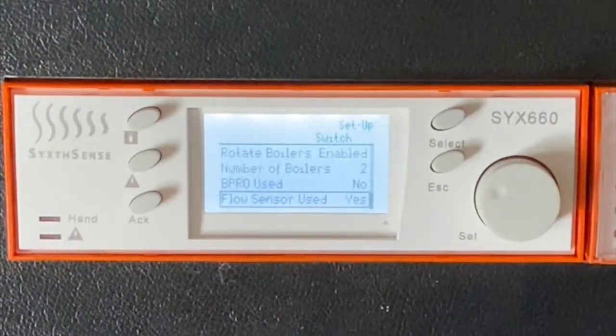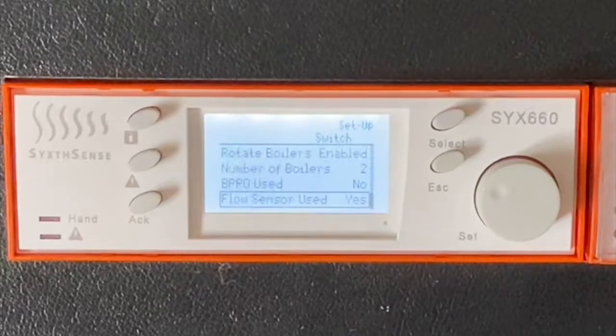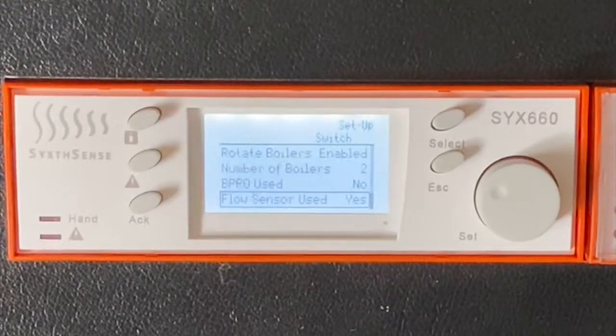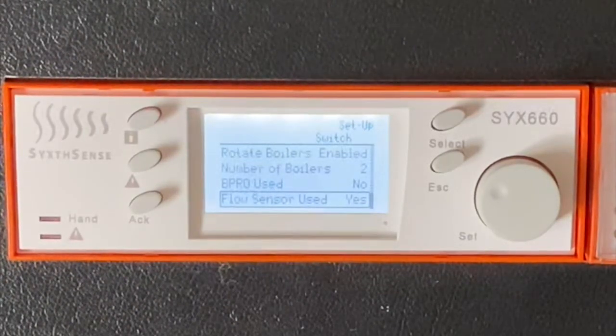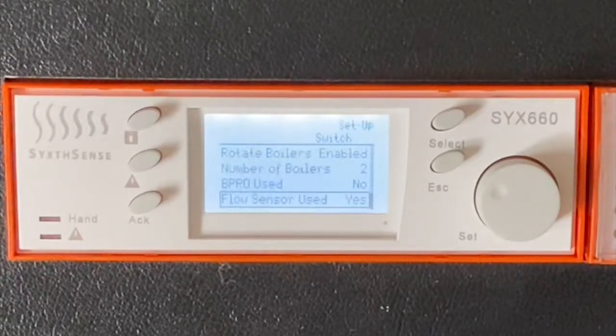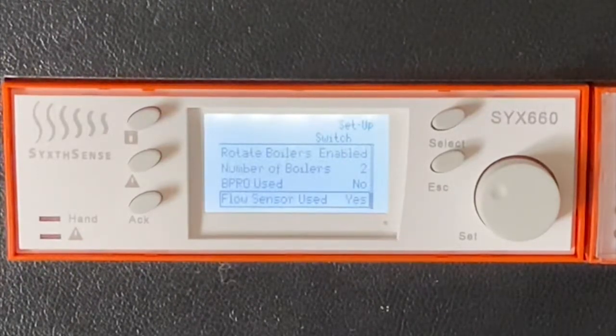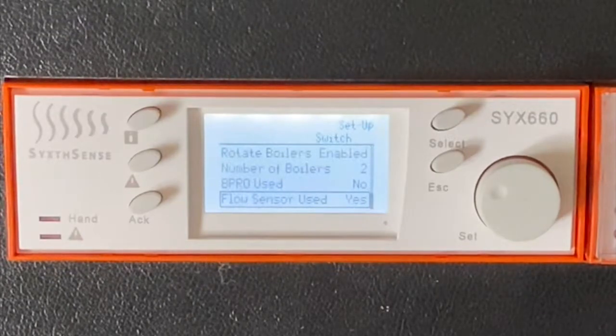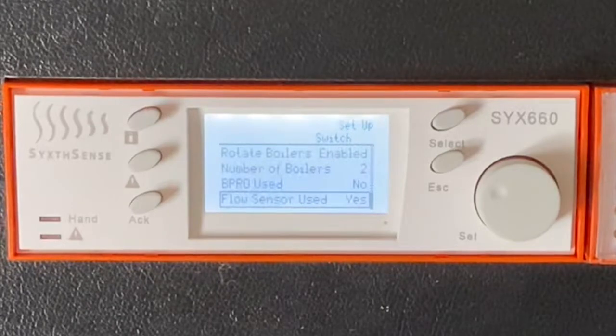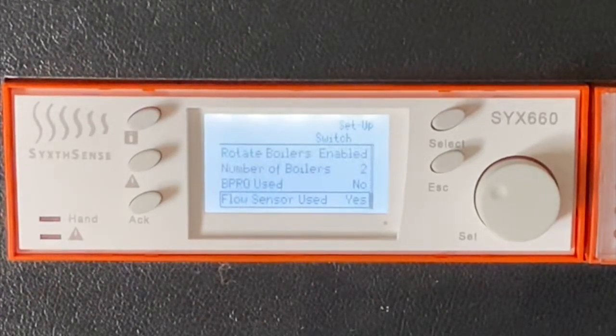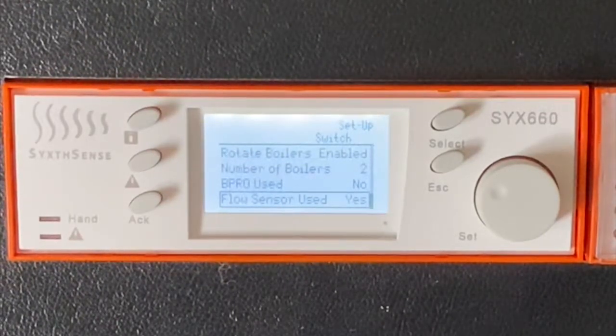We have a flow sensor used. It is the case that sometimes the controllers that we're replacing with an SYX controller may not have a boiler flow sensor. It is by far the most efficient way of operating your system for us to modulate the boilers. So if you can convince the client to have a boiler flow sensor fitted at the time of install, this will pay dividends down the road, because we can match the boiler load to suit the system load throughout the heating period of the year. So we can modulate the boilers to match the relevant demand from the system.